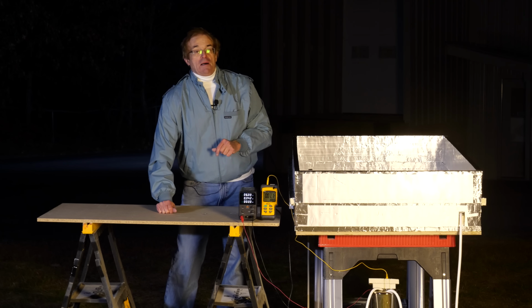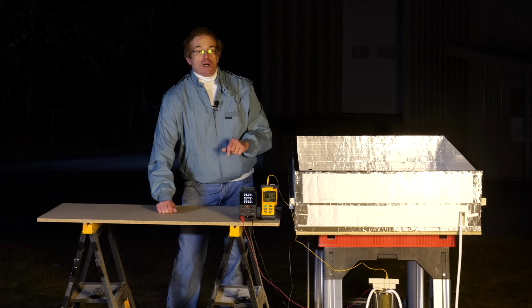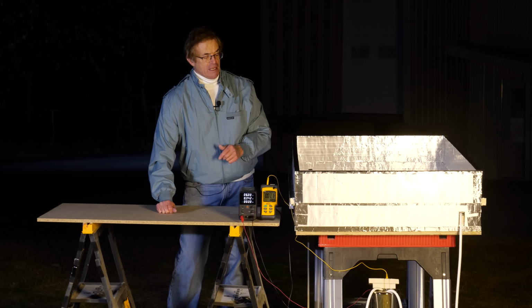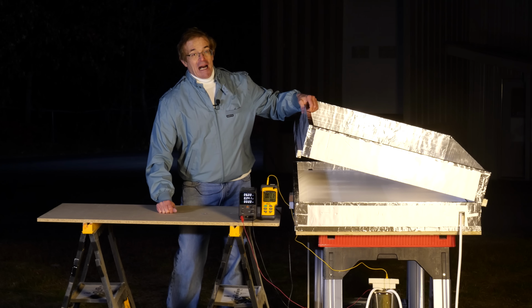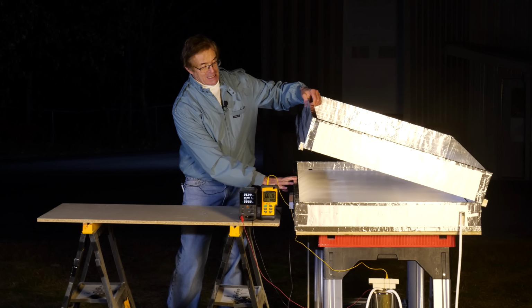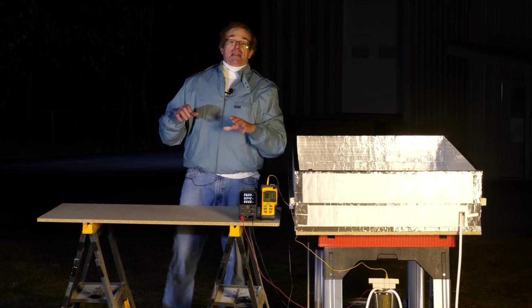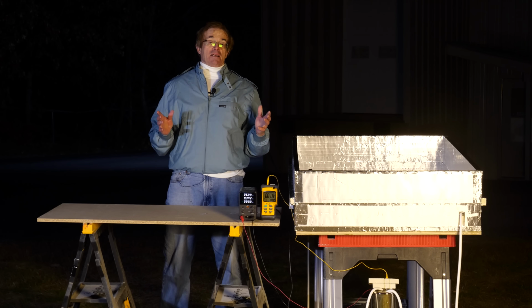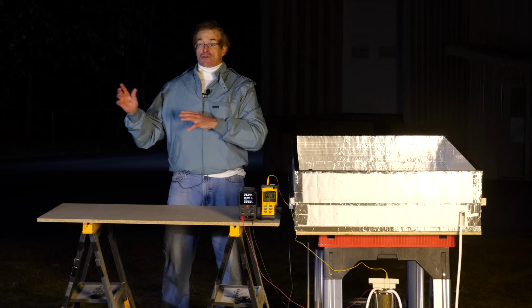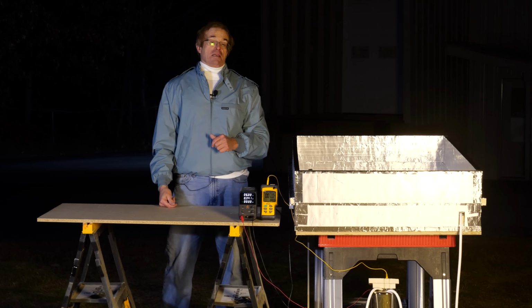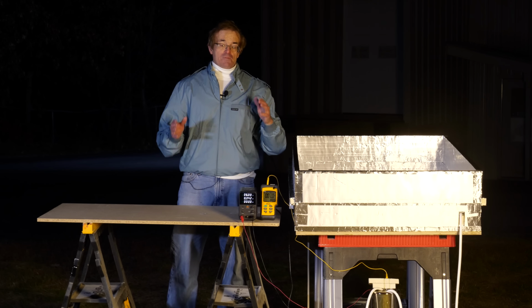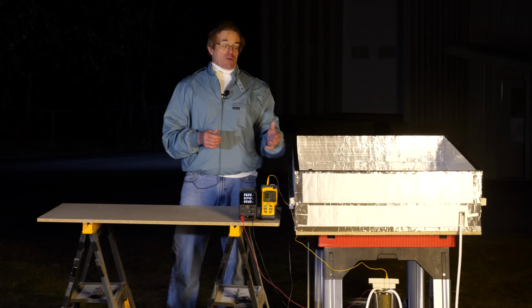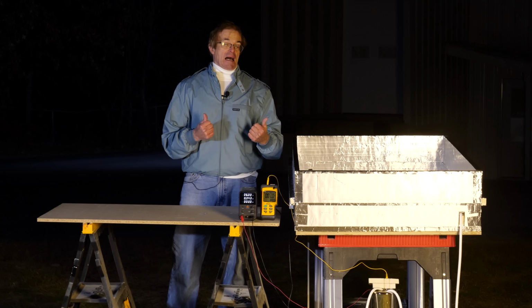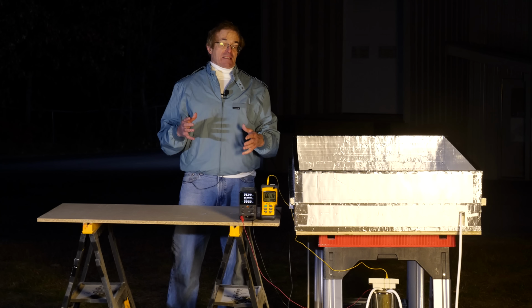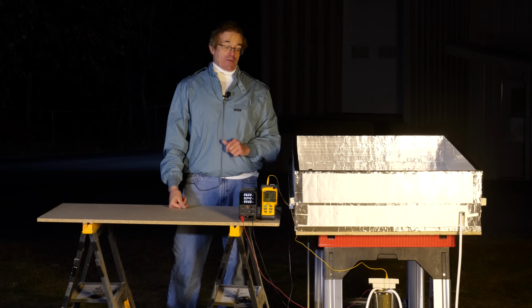The water has a small amount of propylene glycol in it because we are going down to such low temperatures. We don't want the water to freeze in the heat exchanger. You'll also see that I have this upper collar on the box here. This is because we aren't on top of a building or in big sky country. We have a lot of trees and buildings and structures around here that can all radiate infrared radiation down onto the panel. And we want to do the best we can with this chiller to make sure that it only sees the sky. It can radiate its infrared out, but it doesn't get bombarded by infrared from the surroundings.